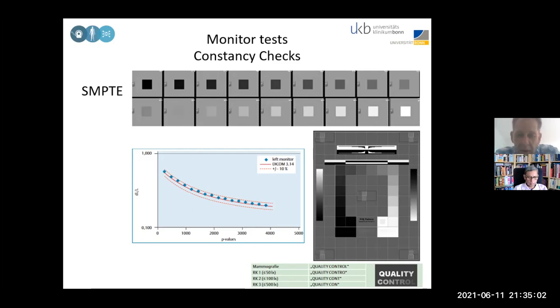And you see there on the very low table that you see in mammography, you should see the word quality control, even on the black, on the white, and on the gray one. And you should see all letters. And I can tell you, we have rooms where you can't see all letters, even though it's the same image, because of the background luminosity of your room. So look at that as well. This is always a parameter you have to check in your quality control.